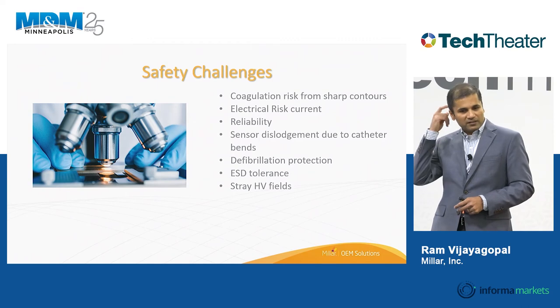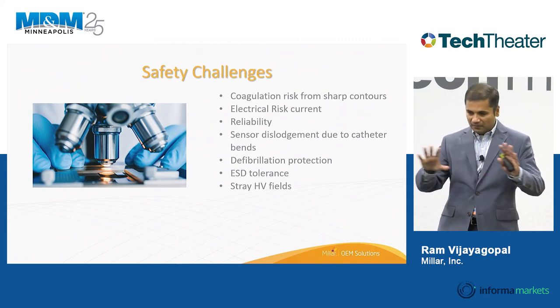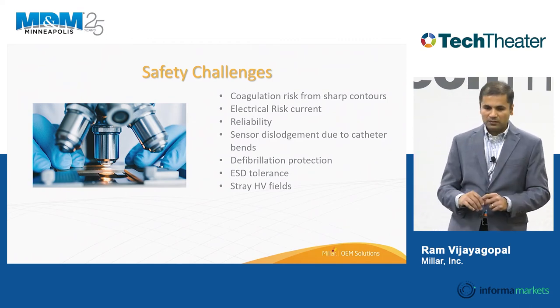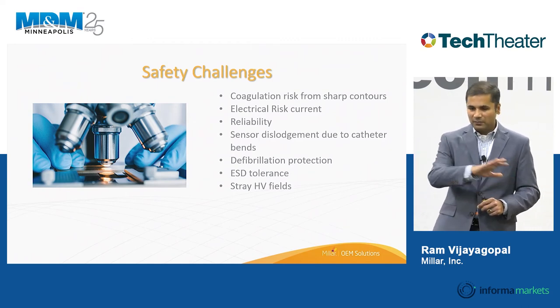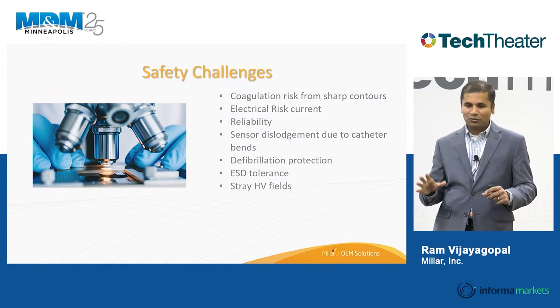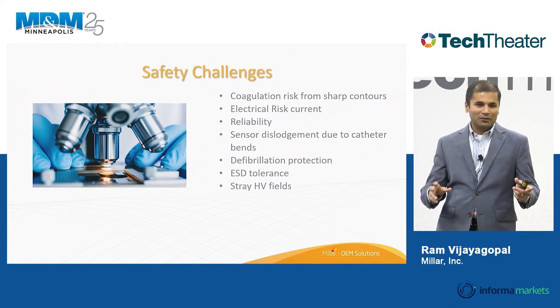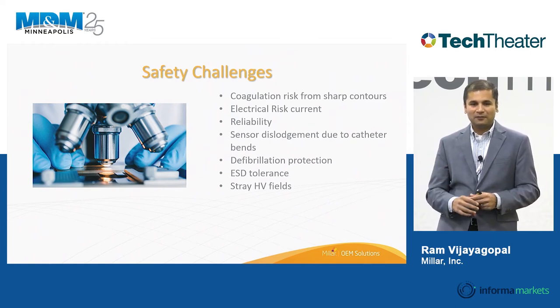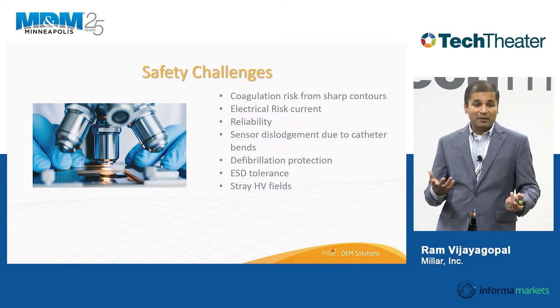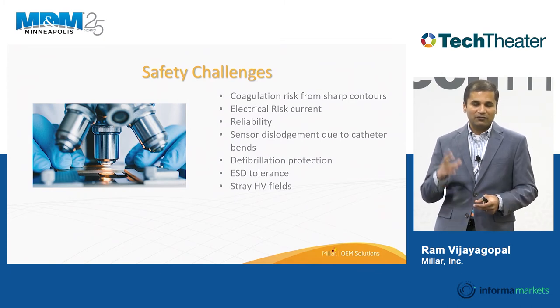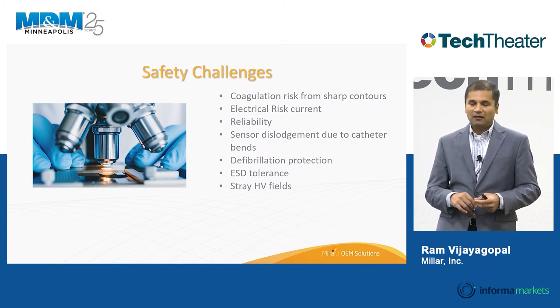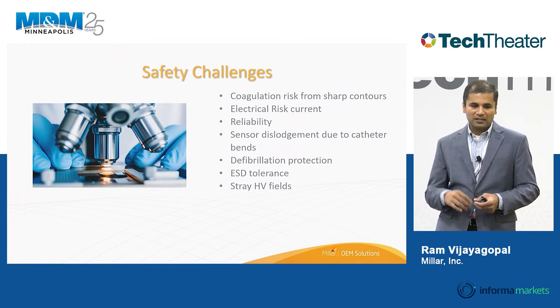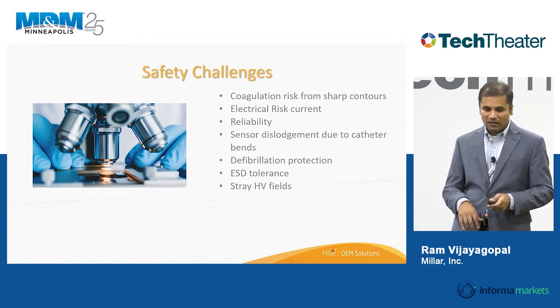Stray high-voltage fields are also a concern in surgical rooms, where there is little control over what equipment is present. It is very common for line voltages to appear on the sensor, even at low current levels — so you need to ensure your sensor can tolerate that.